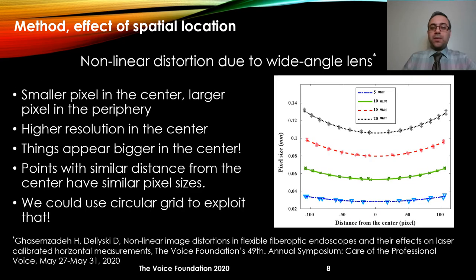Spatial location of the object is another confounding factor we need to account for. In a flexible endoscope, we use a wide-angle lens, and wide-angle lenses introduce non-linear distortion into the images. We have done a separate study on the effect of non-linear distortion. As shown in this figure, when we are at the center of the image, the size of the pixel is minimum, but as we move toward the periphery, the size of the pixel increases.